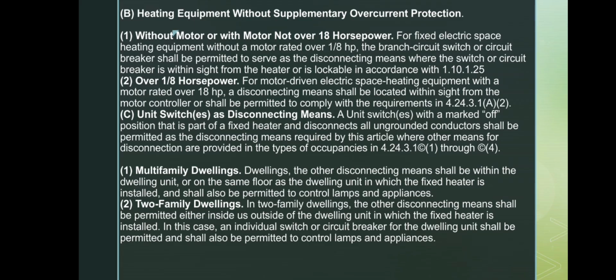Unit switches as disconnecting means. A heater's built-in unit switch marked off may serve as the disconnect, but only if another disconnecting means is available, depending on the type of dwelling. Multi-family dwellings: the other disconnect must be inside the unit or on the same floor, and it may also control lights and appliances. Two-family dwellings: the other disconnect can be inside or outside the unit, and it may also control lights and appliances.